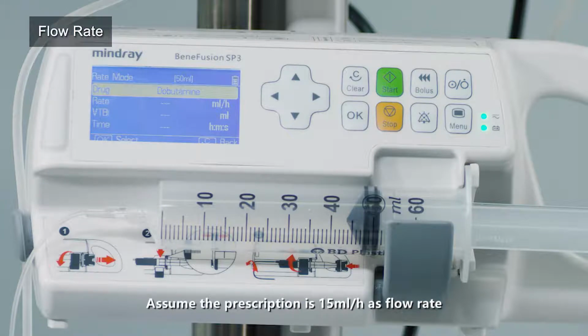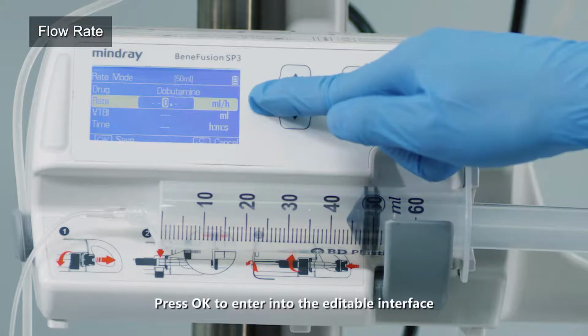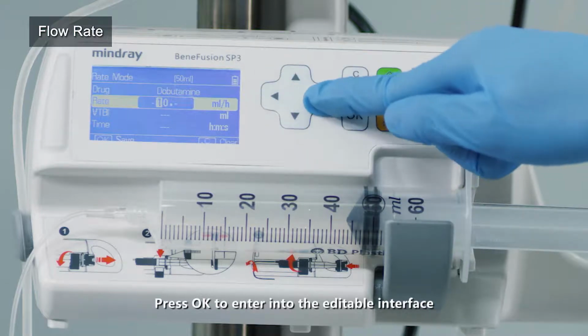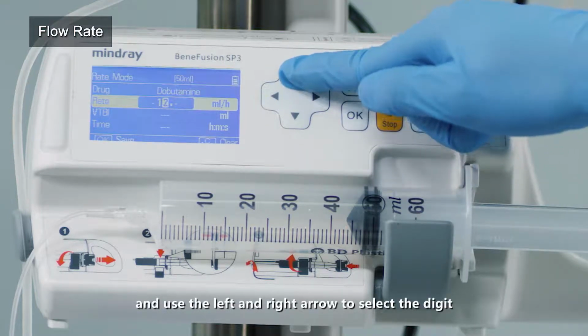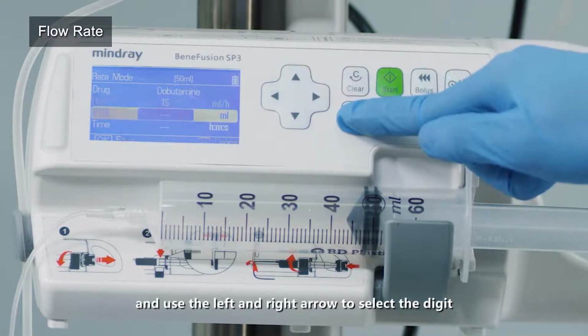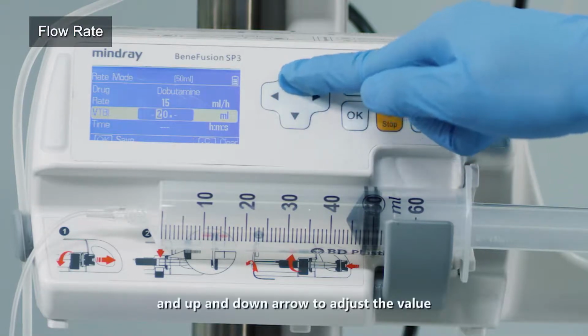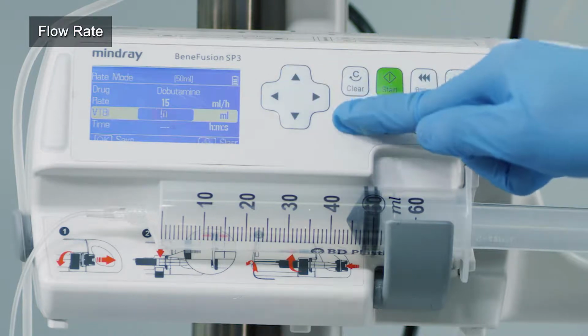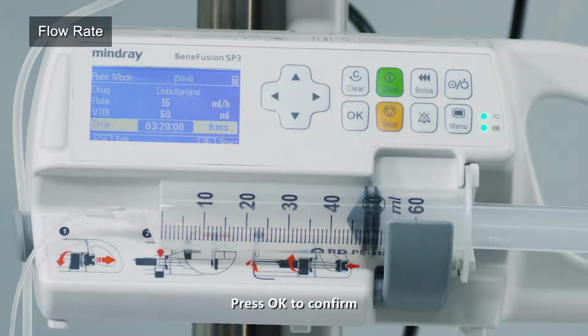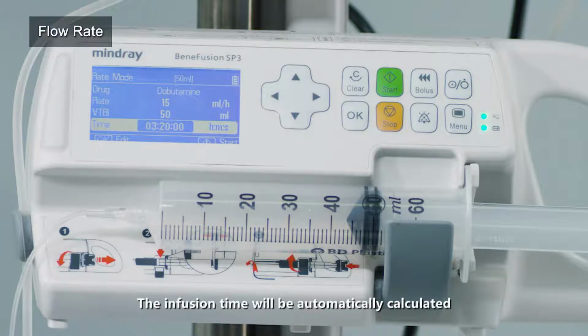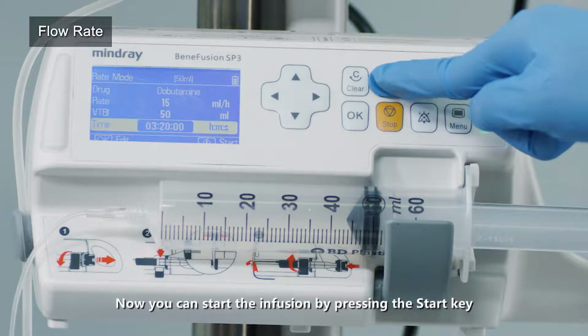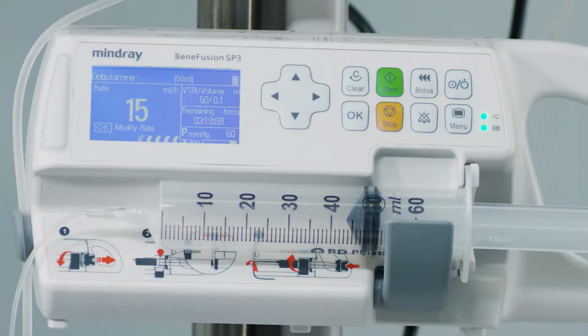Assume the prescription is 15 milliliter per hour as the flow rate and 50 milliliter as the volume to be infused. Press OK to enter the editable interface and use the left and right arrows to select the digit and the up and down arrows to adjust the value. Press OK to confirm. The infusion time will be automatically calculated. Now you can start the infusion by pressing the Start key.